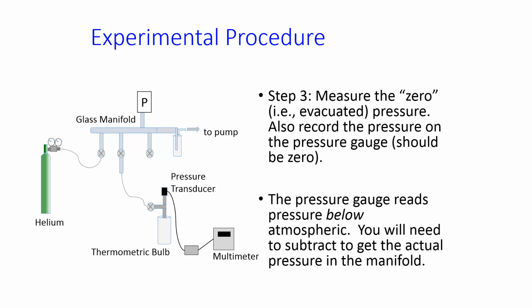You want to measure, both with the pressure gauge and the pressure transducer, the evacuated pressure of your system. It might not be 0 torr, it probably won't be, but it should be very close. So you're going to get this number off of your pressure gauge. You should also get a corresponding voltage from the pressure transducer.